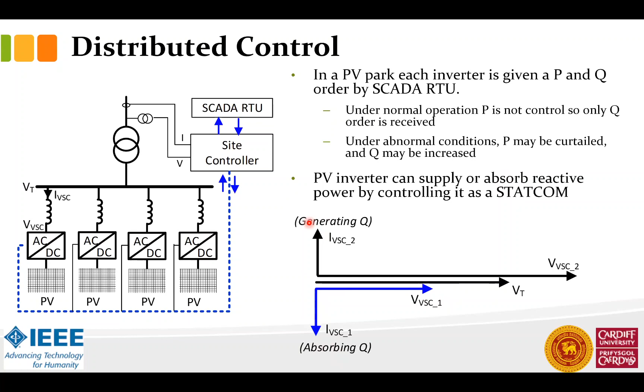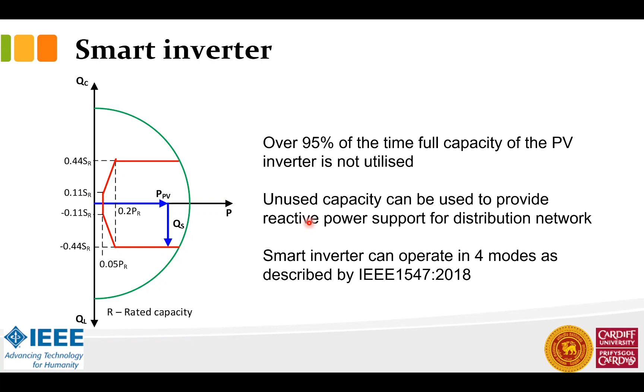By changing the voltage of that inverter, you can either absorb or generate reactive power. Now it has been made mandatory in the latest grid codes or connection codes. In the US, they use IEEE 1547, 2018. In the UK, they use G99 and G98. In Sri Lanka, our grid code, or the connection code for distributed generation, is very old. So we don't have this kind of mandatory reactive power support requirement, but it has now been mandated in other countries.